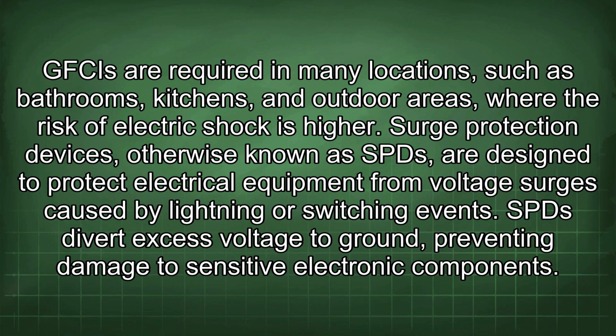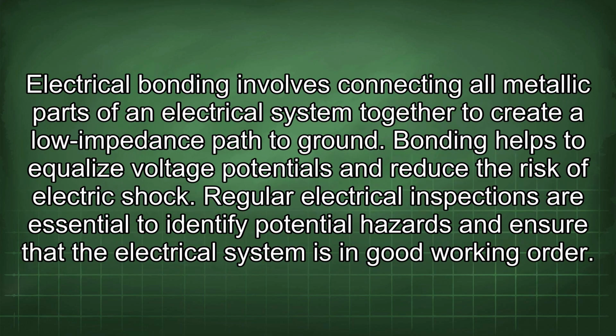Surge protection devices, otherwise known as SPD, are designed to protect electrical equipment from voltage surges caused by lightning or switching events. SPD divert excess voltage to ground, preventing damage to sensitive electronic components. Electrical bonding involves connecting all metallic parts of an electrical system together to create a low impedance path to ground. Bonding helps to equalize voltage potentials and reduce the risk of electric shock.